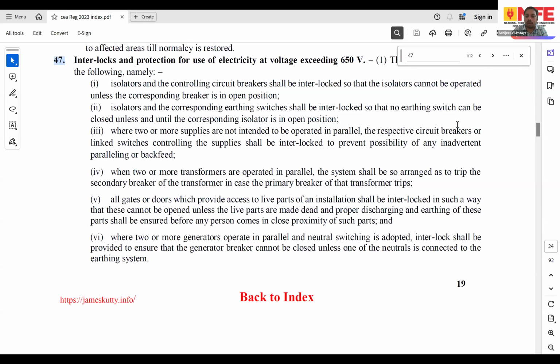So in case you're using a neutral contactor to switch on the neutral, an interlock should be established so that unless the neutral contactor is on, the DG breaker should not get turned on. That would prevent us from damaging the DG through dangerous overvoltages. That is the practice behind it. But the best practice would still be to bring it to a common bus, earth it as common, and have a neutral contactor.